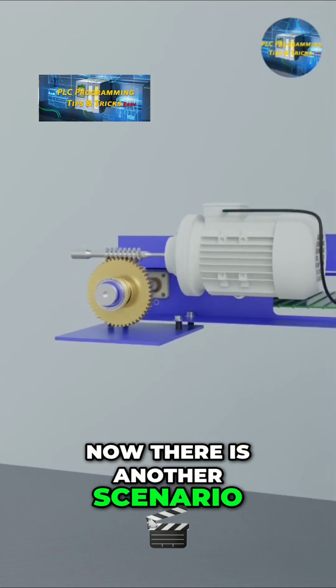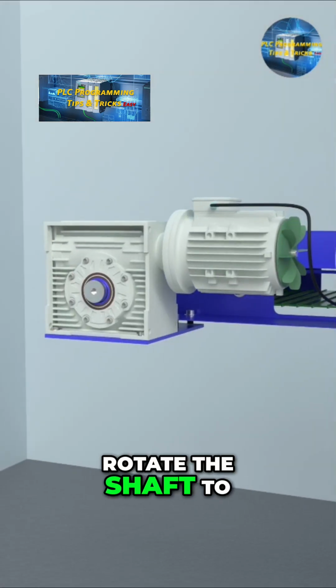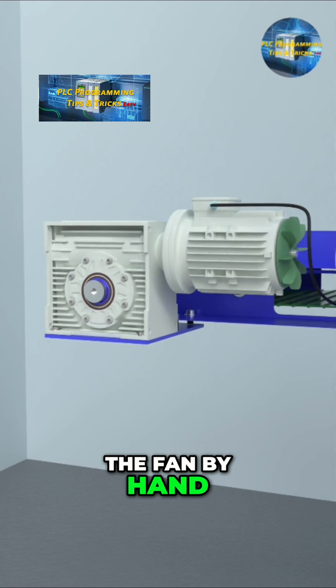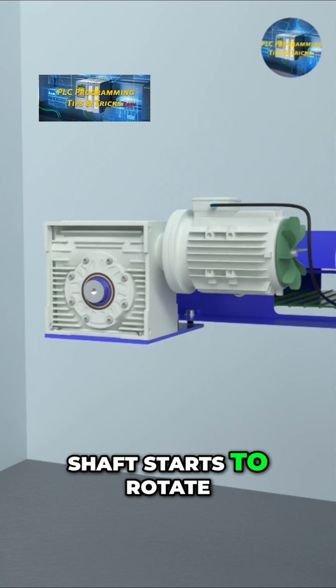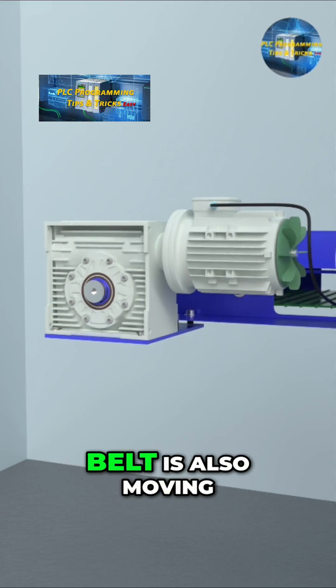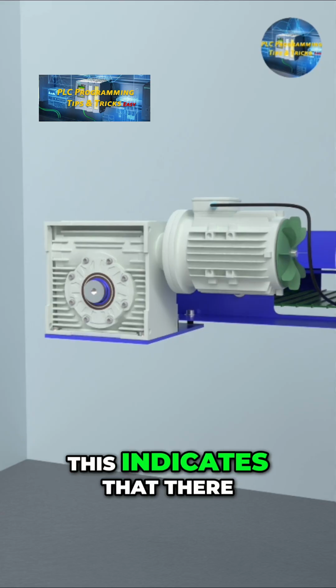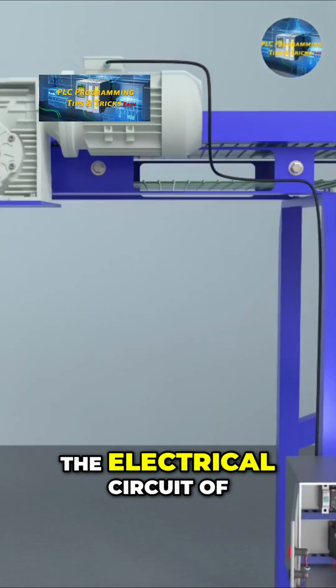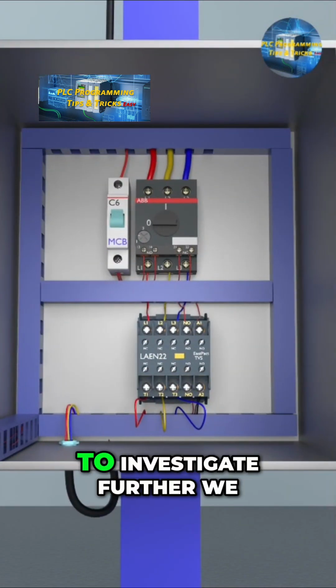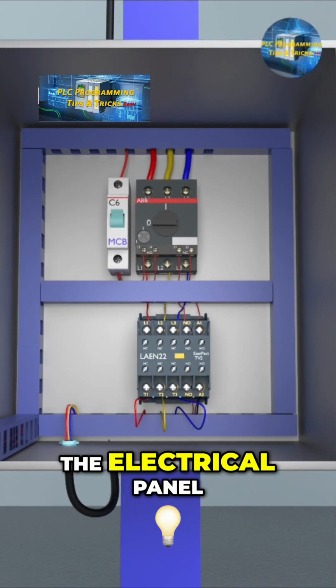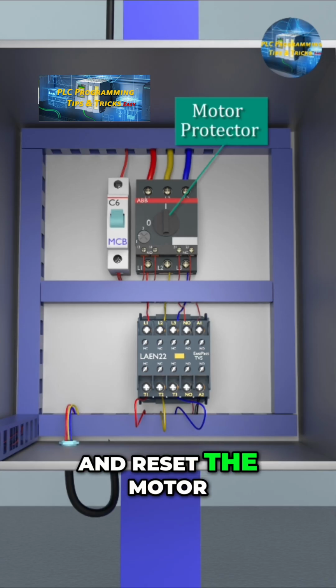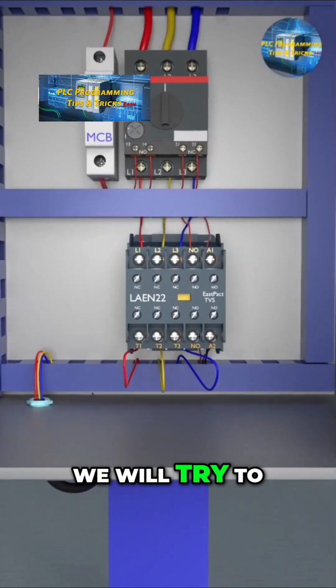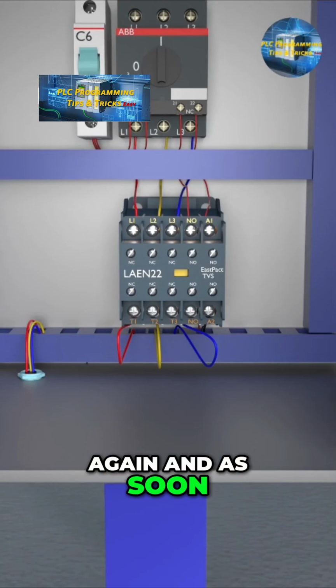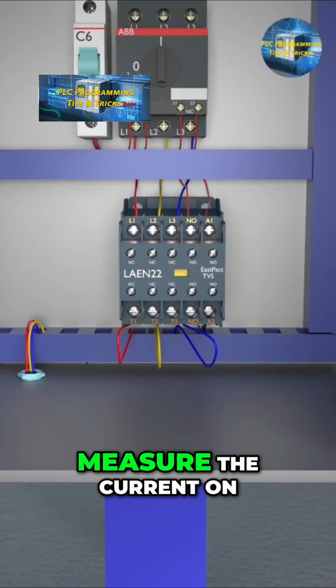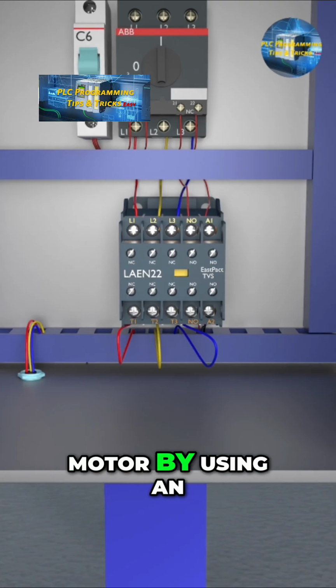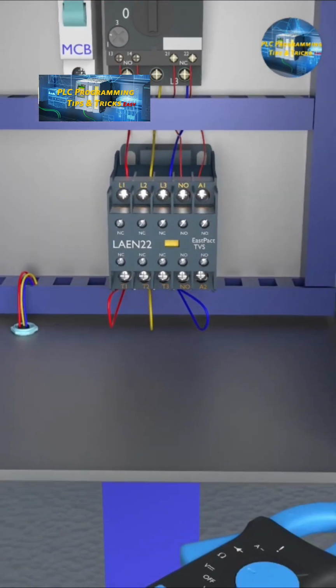Now there is another scenario. If we try to rotate the shaft of the motor by grabbing the fan by hand, and the motor shaft starts to rotate easily and the conveyor belt is also moving, this indicates that there is something wrong in the electrical circuit of the motor. To investigate further, we will go back to the electrical panel and reset the motor protector breaker. We will try to run the motor once again, and as soon as the motor runs, we will measure the current on each phase of the motor using an AC clamp meter.